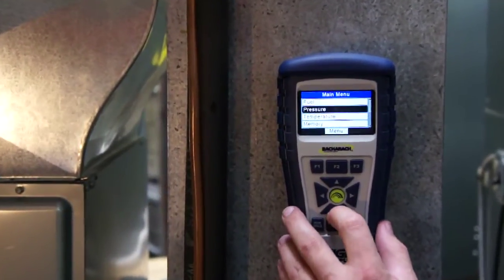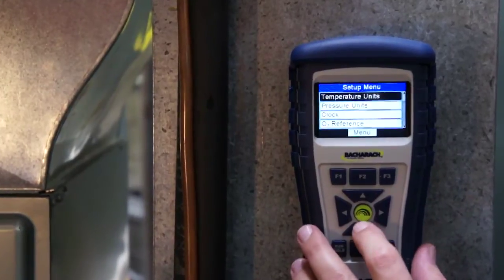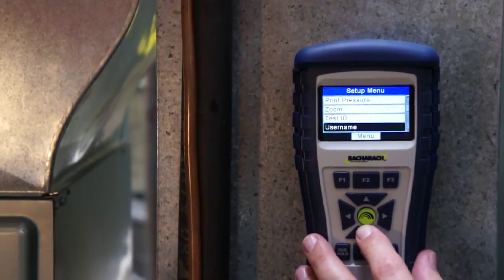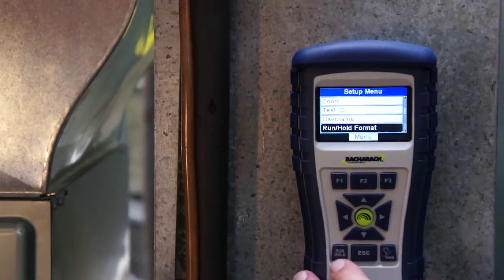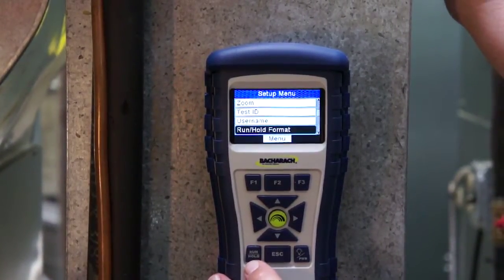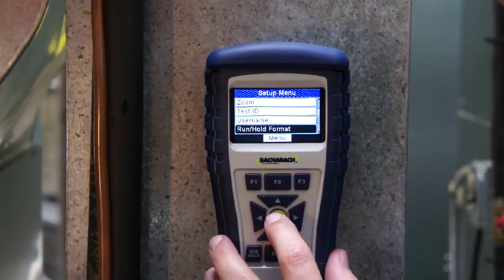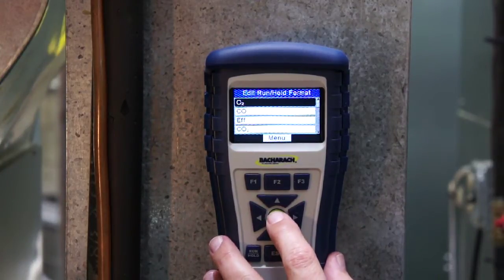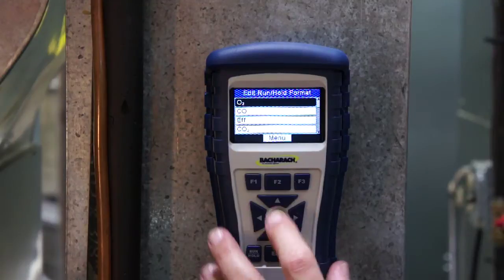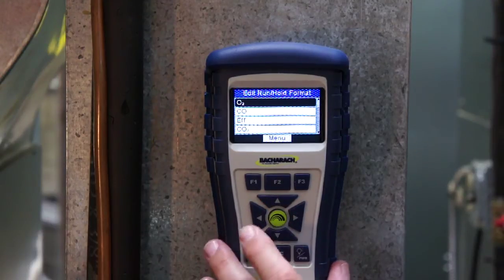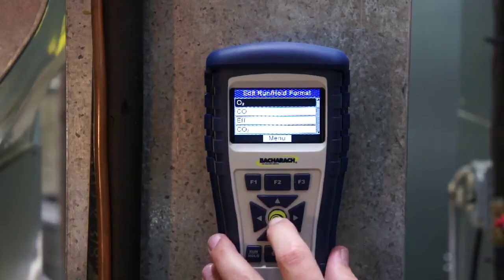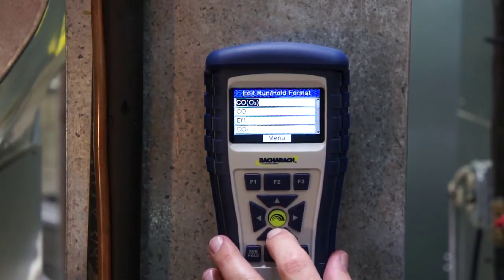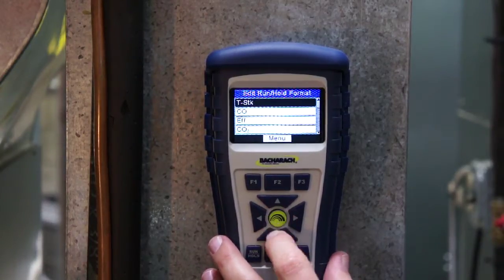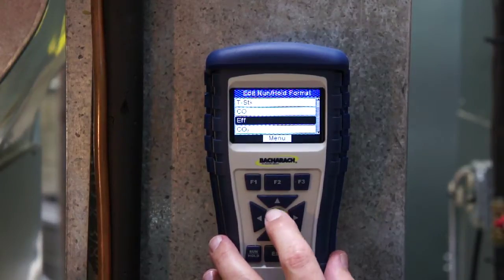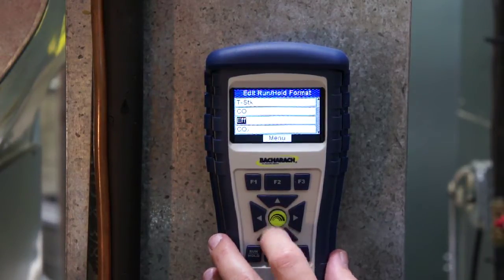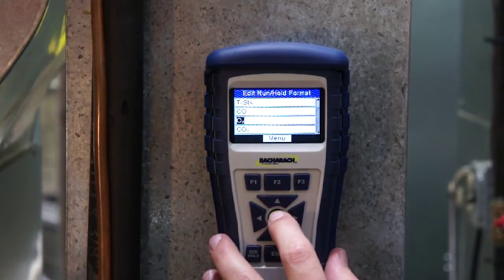I'm going to scroll down again to setup, and I'm going to scroll down until I get to the run hold format. Just like the run hold button shows you, run hold everything on display, it's run hold format. It's going to show us that menu. So I can go in here and edit that format, and I can change these to whatever I want in whatever order I want. So if I really like to start off with stack temperature, I'm going to hit enter here, and I'm going to scroll till I see stack temperature, temperature stack, hit enter. Then I want CO, okay. Then maybe I want to put O2 here, hit enter again, configure that to O2, hit enter.